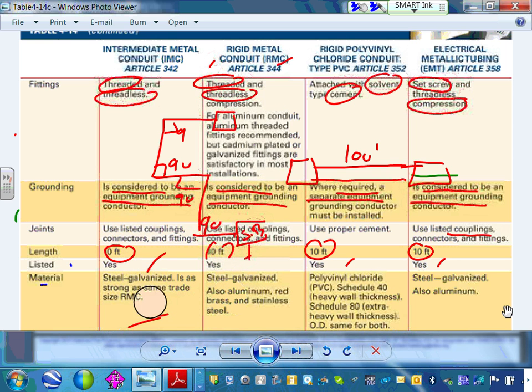By UL. Okay, material. Look at the material they make them from. This is really interesting as opposed to corrosion. You can have steel galvanized or aluminum for the rigid and the intermediate. PVC, of course, is PVC 40 or 80.